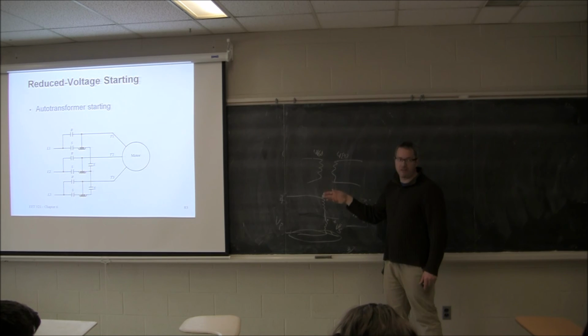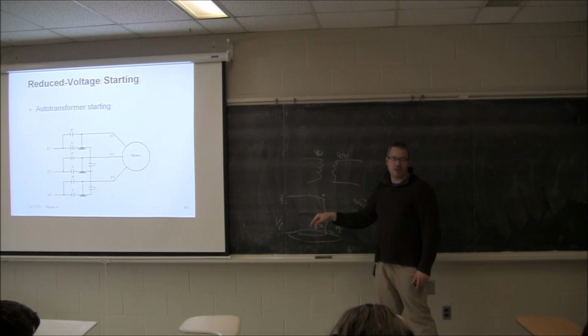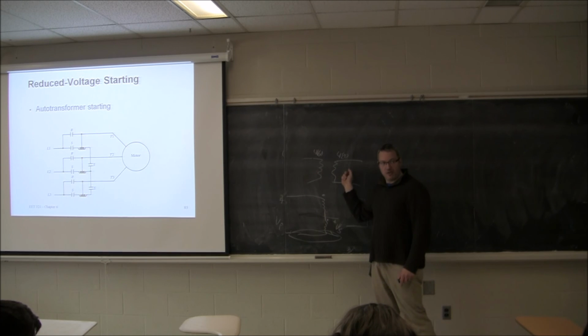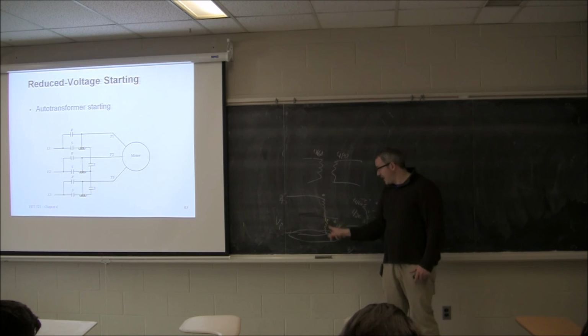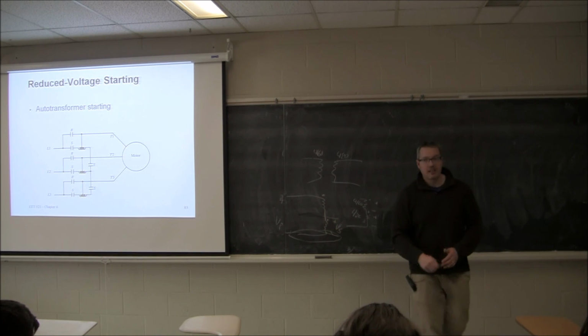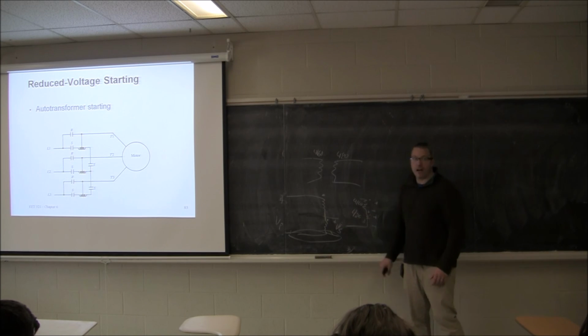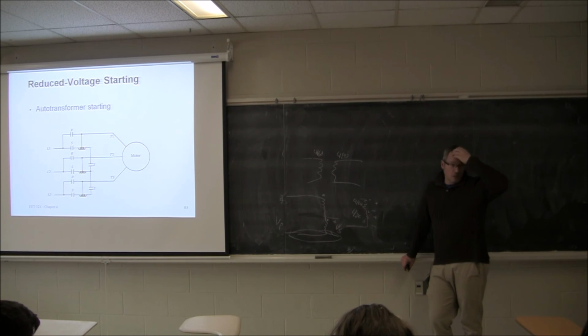There's no path of return. So anything can happen on either side, and you're not passing 4160 onto the secondary side and blowing somebody's house up. Over here, if you have a fault inside these windings, I can be pulling 345 kV to the secondary side. So that's why you usually don't have big changes in voltages.